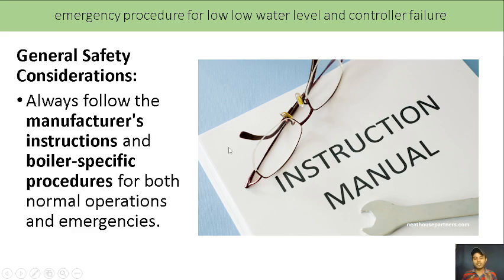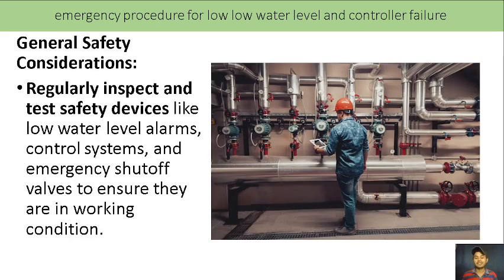Okay, so general safety considerations. Always follow the manufacturer's instructions and boiler-specific procedures for both normal operations and emergencies. So we have a manual on board, so always read it, always follow it. Next, regularly inspect and test safety devices like low water level alarms, control systems, safety valves, emergency shut-off valves to ensure they are in working condition. Also, the electrical emergency shutdown. Regularly inspect and test these devices because these are the devices that will protect us, protect the equipment, and protect the environment from possible damage.